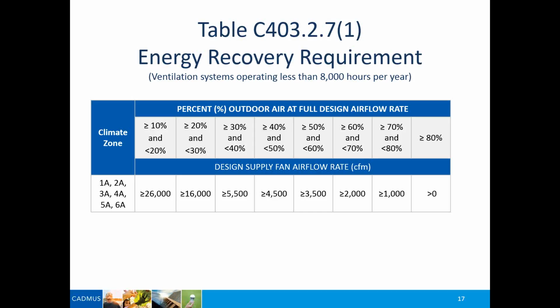So they actually might operate less than 8,000 hours per year. But if you have a building that is either 24 hours a day operation or standard occupancy, maybe open for 10 hours a day, you know that it's going to be providing ventilation air for probably more than 8,000 hours a year. So the way this table works is you have how much outside air you're planning on bringing in, and then your design supply airflow. If my system is operating less than 8,000 hours a year, for example, and I'm bringing in 20% outside air, then in order for me to have to comply with this, my fan system would have to be at least 16,000 CFM.